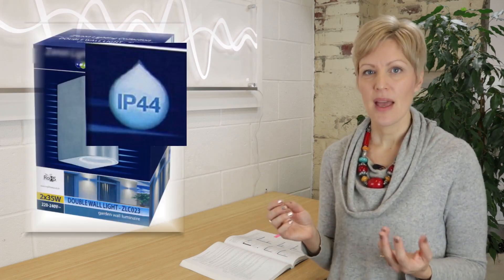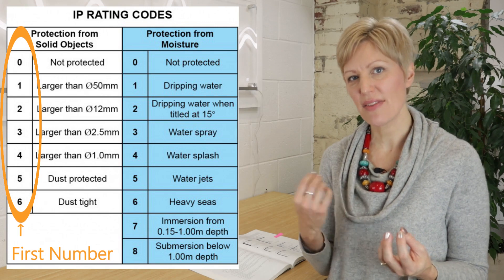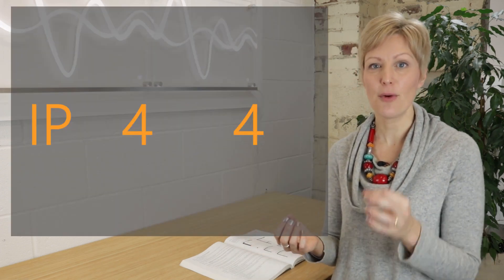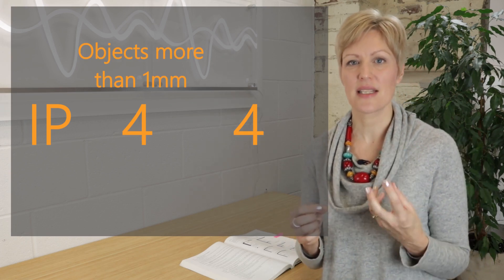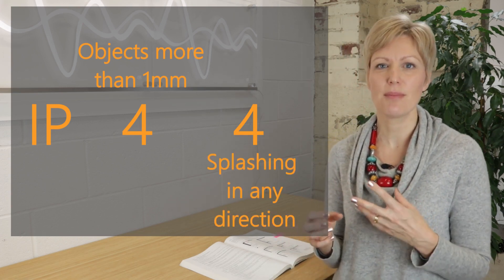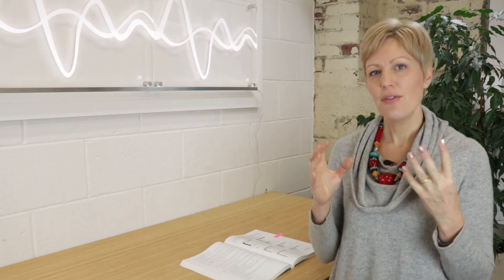Next is the IP rating, which stands for ingress protection. You'll see this code on a lot of products — something like IP44. The first number stands for the degree of protection against solid objects, and the second number for the degree of protection against water, which is really the one we're interested in here, because as we know, water and electricity do not mix. For example, a product which is IP44: the first four means it's protected against objects larger than one millimeter big, and the second four means protection from splashing from all directions.